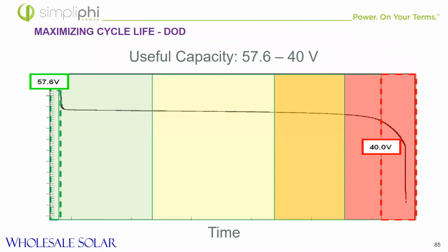This discharge curve illustrates the full available operating range for a 48 volt battery. Note the smooth and continuous discharge curve. The curve peaks at approximately 58 volts and sweeps down to its complete duration at 36 volts. But the actual useful portion of the battery is between 57.6 and 40 volts. Usually at 40 volts, we'll do a low battery voltage cutoff.